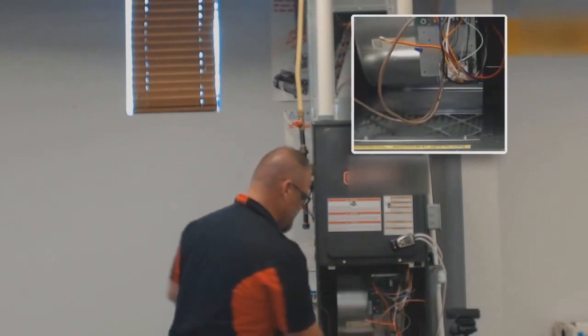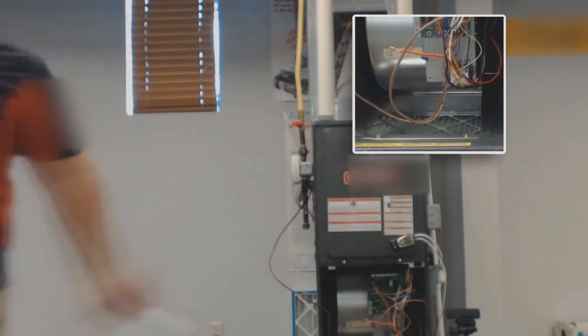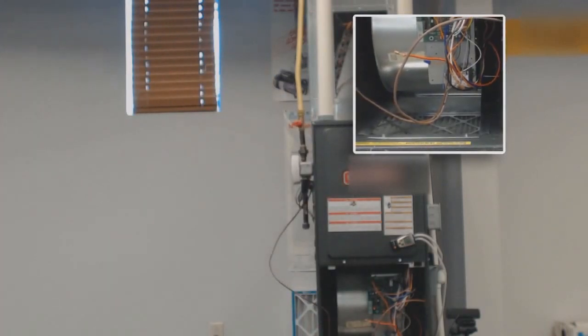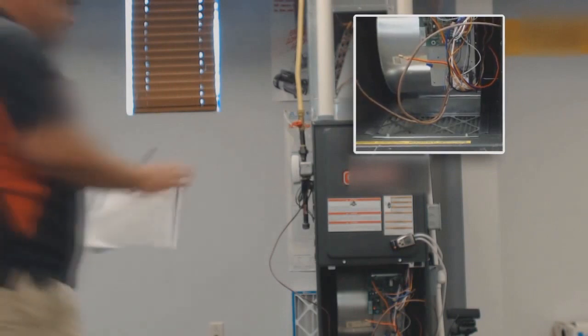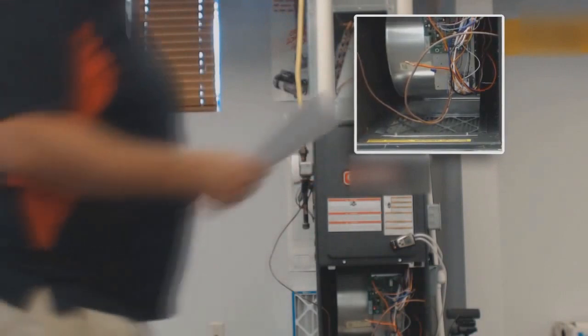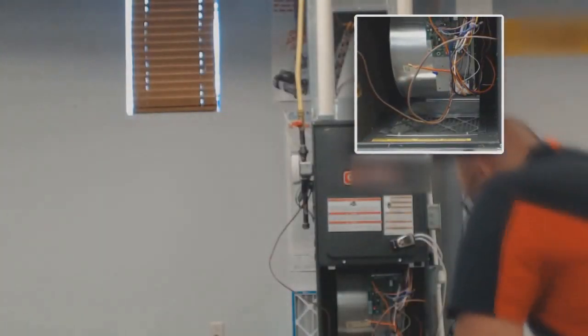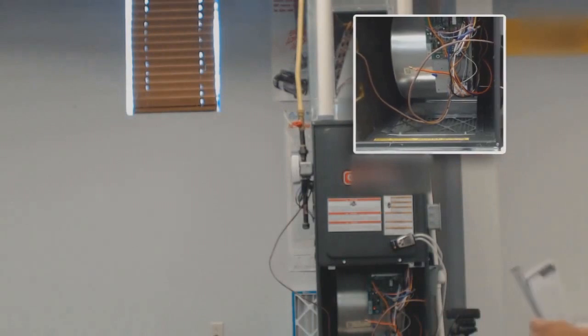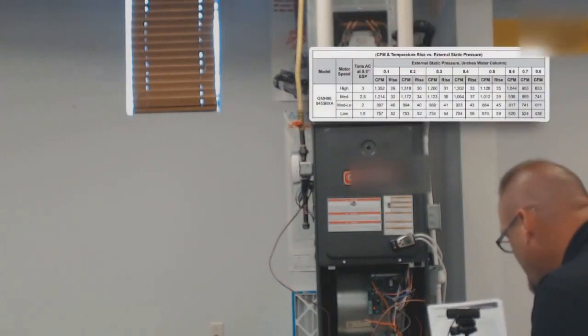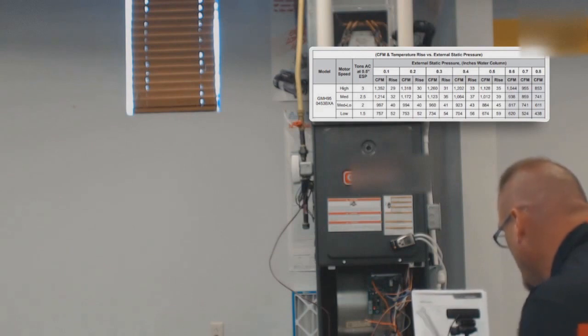Now what we're trying to figure out is which of those speeds is going to be the proper setup for this furnace for the air conditioning speed. Now in doing that, we have to make sure that we set everything up properly according to the manufacturer's guidelines. And the manufacturer's guidelines tell us that we've got to make sure and set it up according to the blower performance data, like you see on this chart. The particular furnace that we're working with is GMH9545. You can see it says high, medium, and low speed.